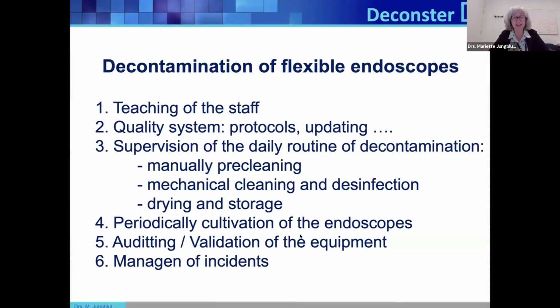So manual pre-cleaning, as Jill and Basra told us, the IFU is extended to sometimes more than 100 pages, and we can't know everything. Anyway, at a hospital or at the endoscope area, we have a certain possibility to work. We cannot work through 100 pages each time. So manual pre-cleaning has to be in a standardized way, and we have to always do the same, with the same movements, same steps, one after another. We have to repeat it. And our colleague has to tell us, oh, by the way, you forgot to brush, or by the way, there is another thing on it, there is a little dirt. We have to check on each other.